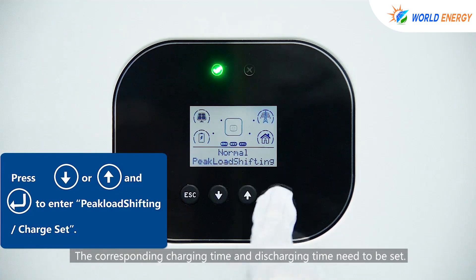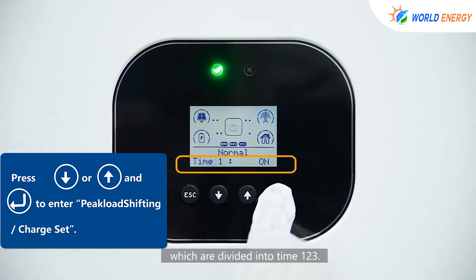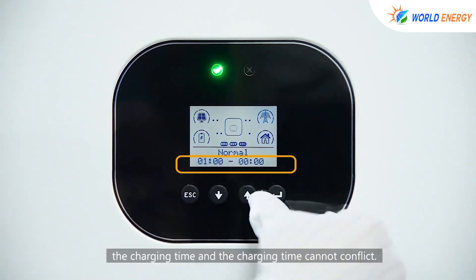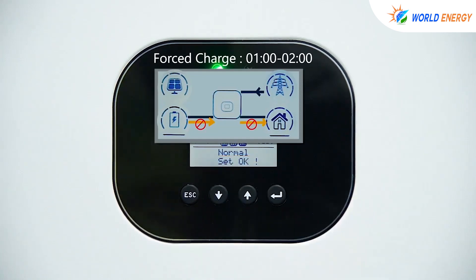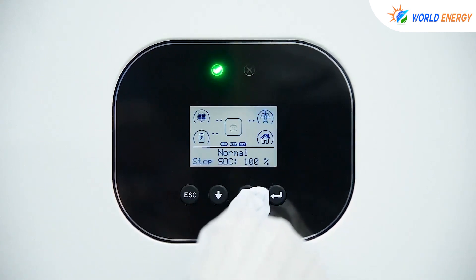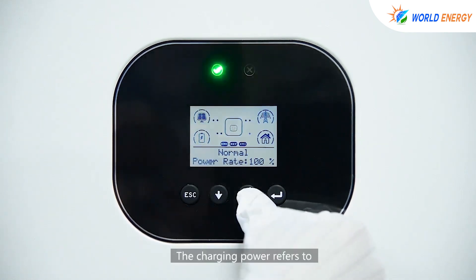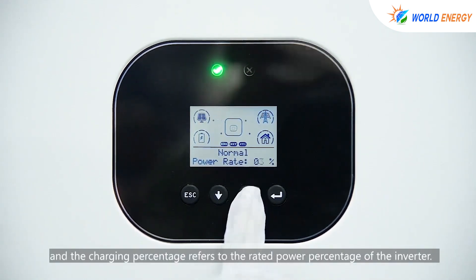The corresponding charging time and discharging time need to be set, divided into three time periods: time 1, 2, and 3. During the charging time, note that the charging time and discharging time cannot conflict. The charging SOC is when the battery stops charging and can be set according to needs. The charging power refers to the charging power of the inverter to the battery, and the charging percentage refers to the rated power percentage of the inverter.